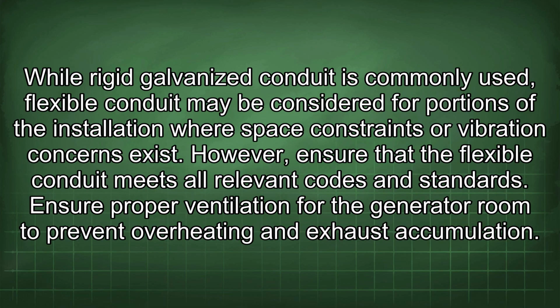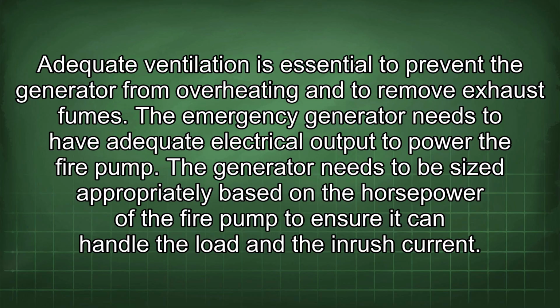While rigid galvanized conduit is commonly used, flexible conduit may be considered for portions of the installation where space constraints or vibration concerns exist. However, ensure that the flexible conduit meets all relevant codes and standards. Ensure proper ventilation for the generator room to prevent overheating and exhaust accumulation. Adequate ventilation is essential to prevent the generator from overheating and to remove exhaust fumes.